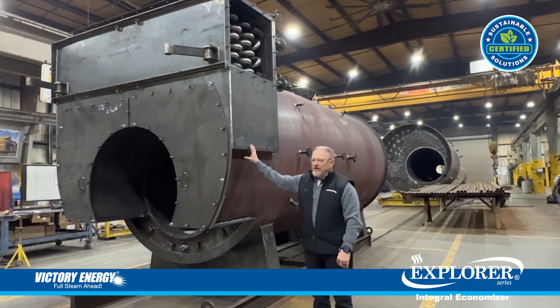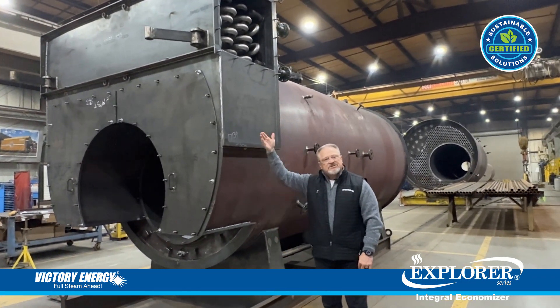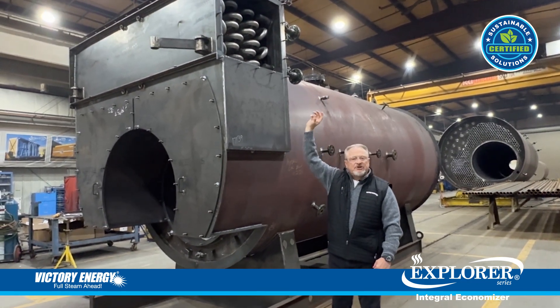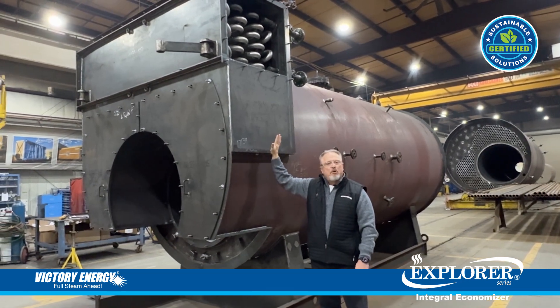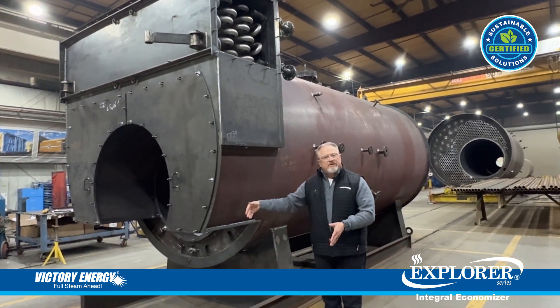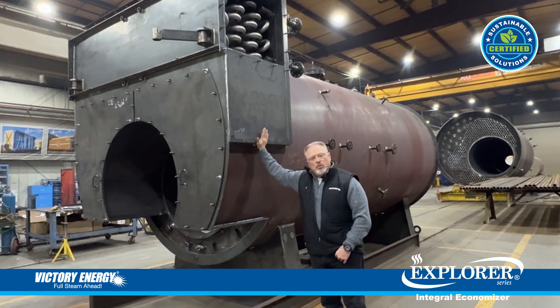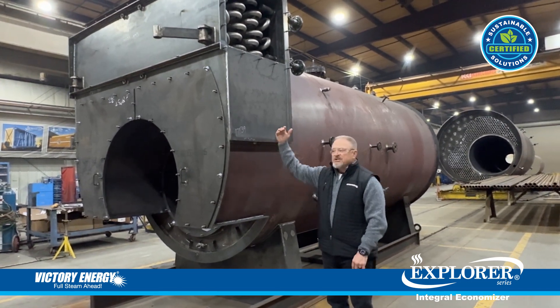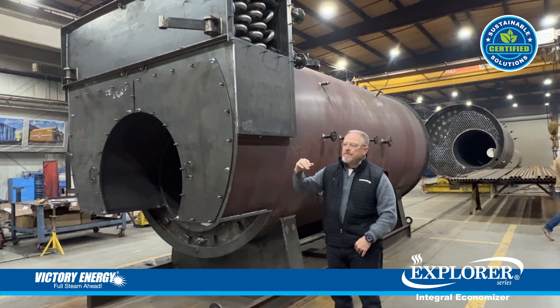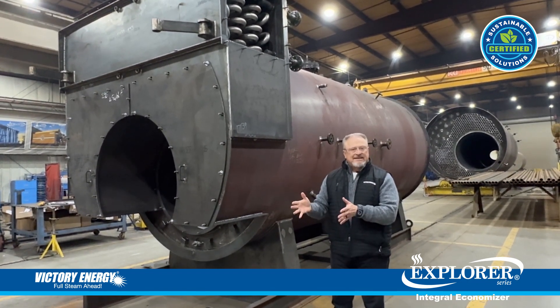Another large benefit: when you have an external economizer plus a stack sitting on top, you typically need a support steel structure on the outside of the boiler to carry the weight of that economizer and stack — not placing it on the smoke box. With an existing plant that may be limited in width beside the boiler room wall, this technology eliminates that support steel structure, as long as the stack is 30 feet or less in length. That's a great advantage and helps keep the overall footprint of the boiler package neat and compact for the customer.